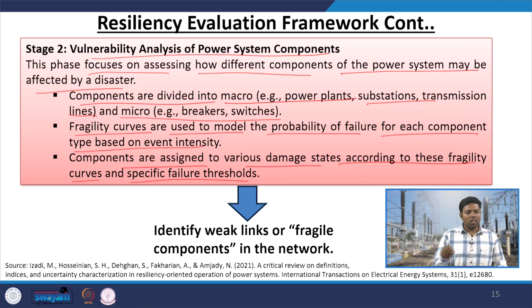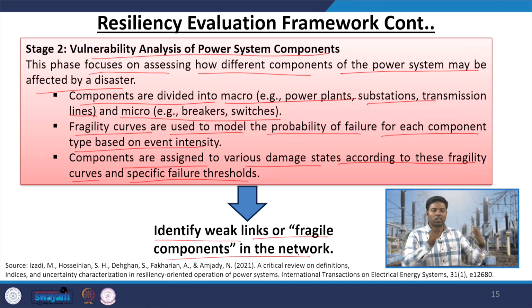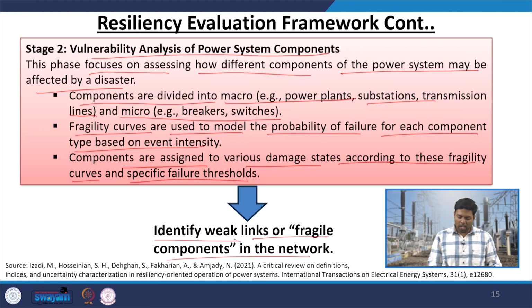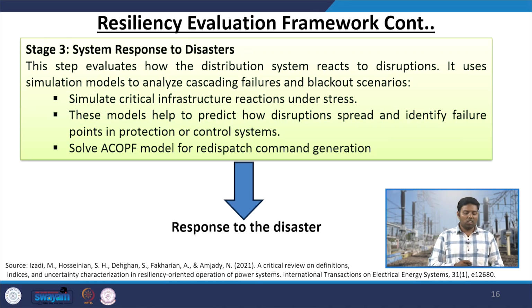As an output of stage 2, you identify weak links or fragile components in the network. So first you identified the disaster, then simulated your power system components against that disaster to see if your system is vulnerable. If it is vulnerable, you find which poles, lines, or substations are more vulnerable when exposed to such events, and feed those identified weak links into stage 3.